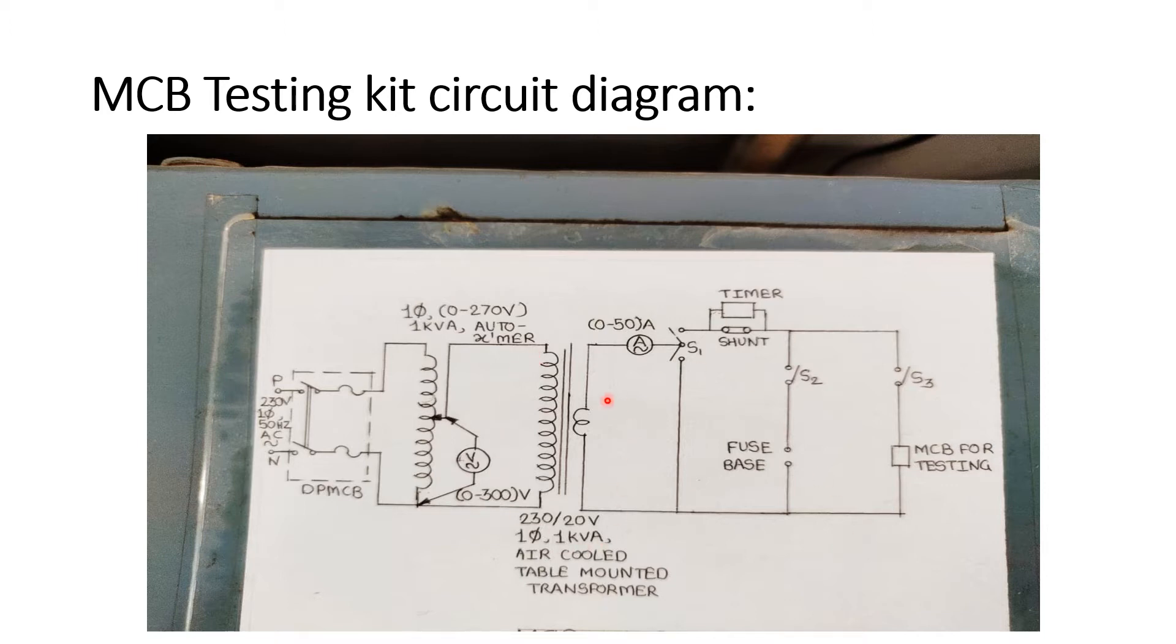So here one transformer is there which is available inside that particular kit. And on the secondary of that particular transformer we are having different switches. So as I shown you S1, S2 and S3. So you are able to conduct a short circuit test just by pressing S1 on. If you want to perform fuse test then with the help of this second switch you will be able to carry out fuse test. But as our interest is in testing MCB today we are going to operate only switch number three that is S3.